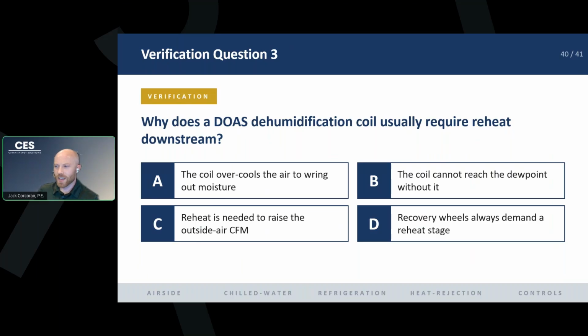And the answer is A. All three answers were A. So the coil overcools the air to wring out the moisture. Yeah, right. If you are dumping that really, really cold air, because we need to, right? Our coil is very, very cold to get rid of the moisture, but it also makes your air sensibly super, super cold. Your dry bulb temperature is very low, and there's risk of having condensation in your space. So the answer is A. You're going to want to have reheat if you wring out the air and you overcool it.